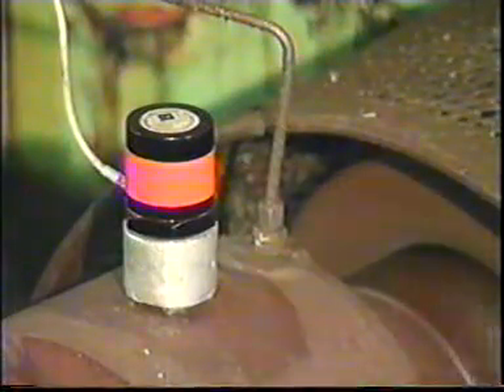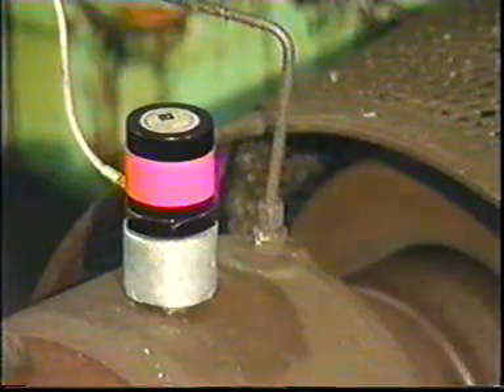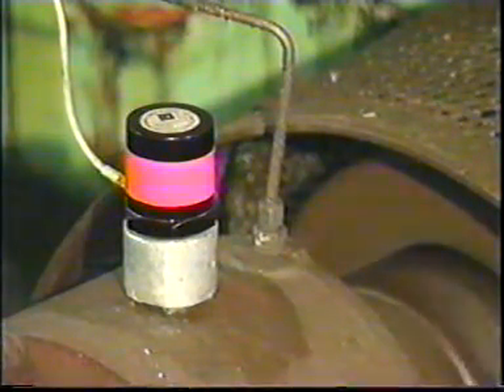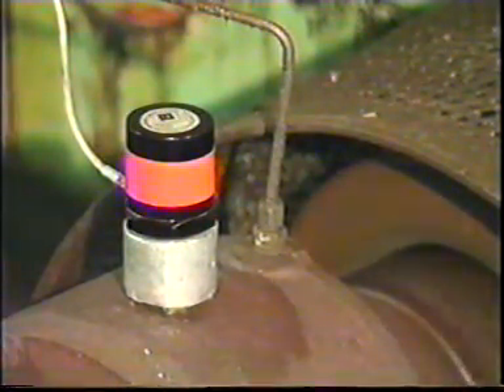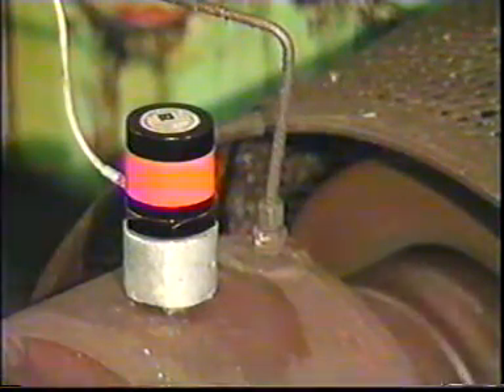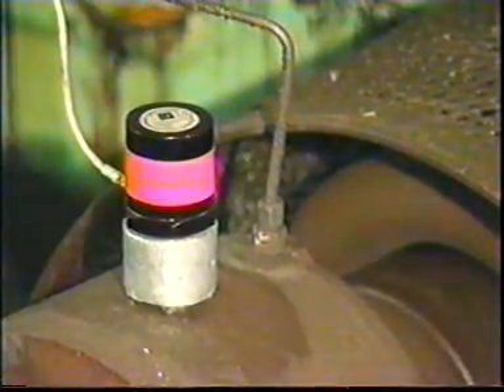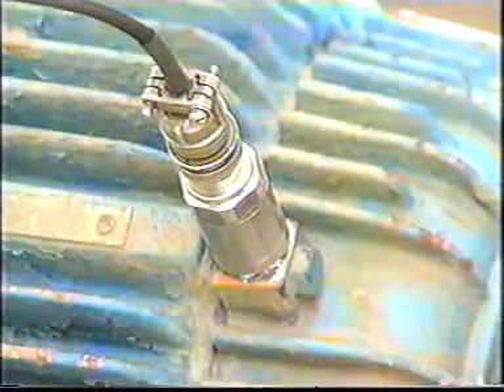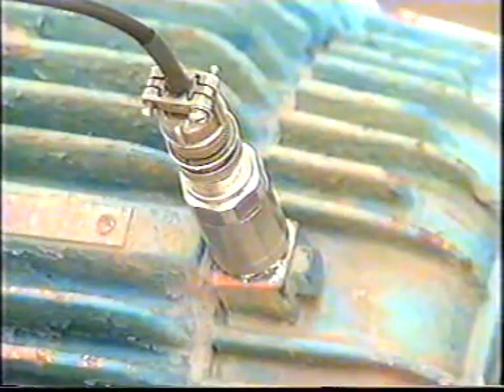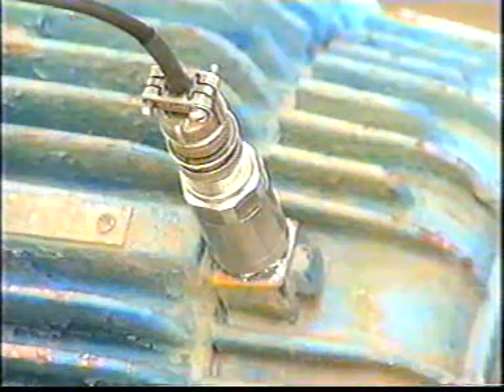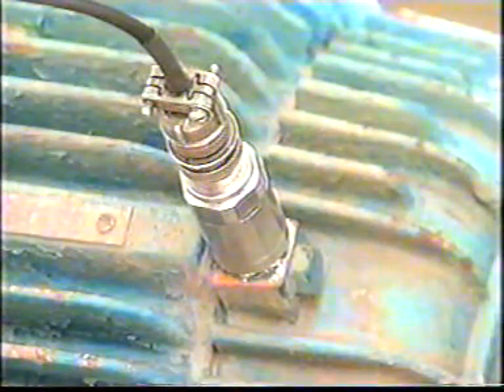Velocity probes are susceptible to sensitivity changes due to temperature and wear. As the temperature changes, oil viscosity in the velocity probe changes. Springs can lose elasticity. Accelerometers are rugged, but the crystals can crack if the sensor is dropped or if temperature limits are exceeded.